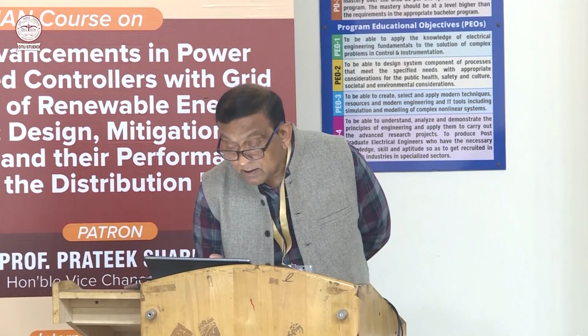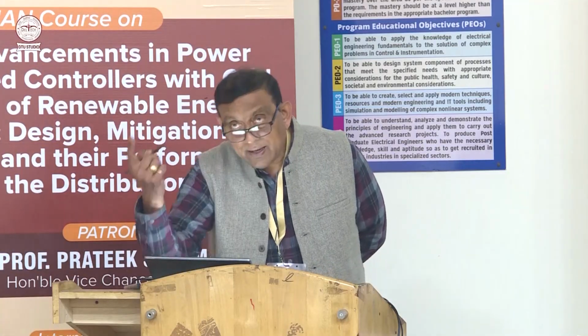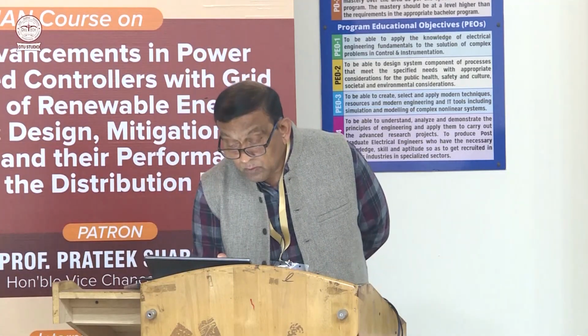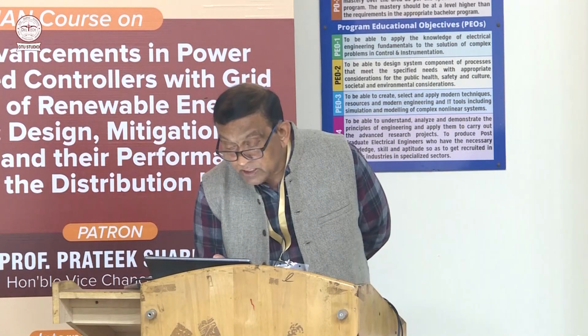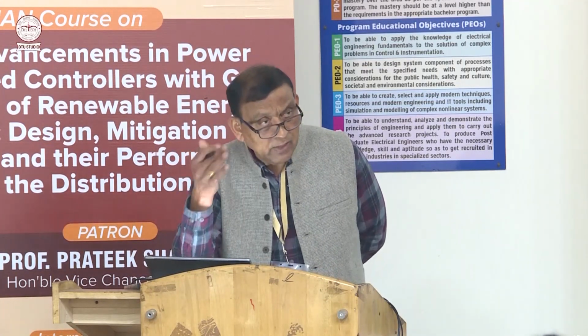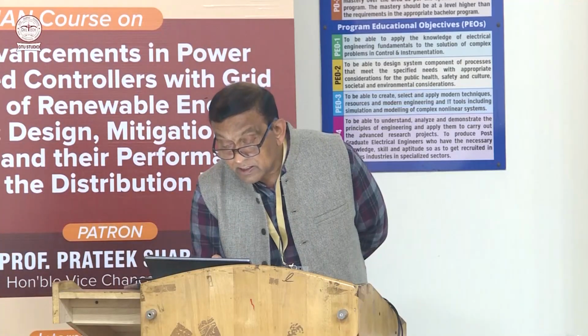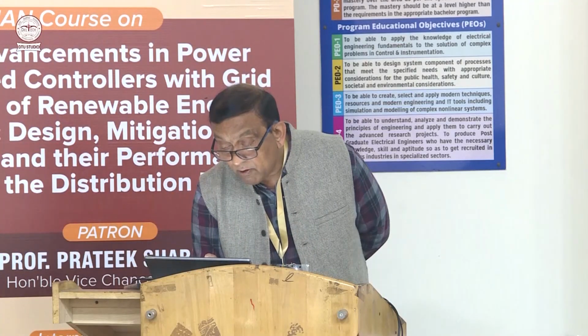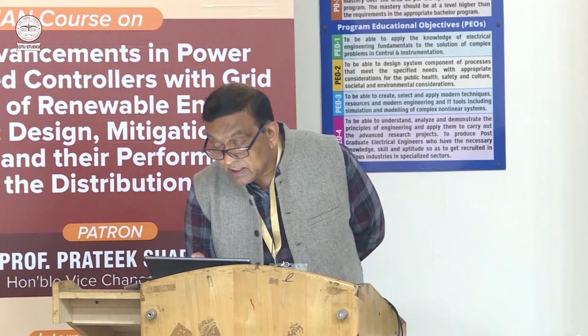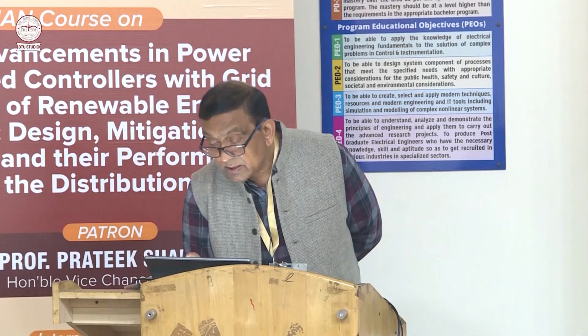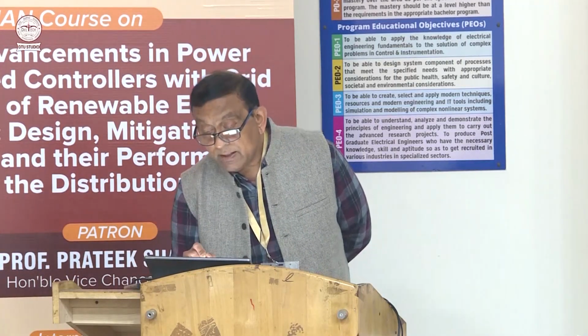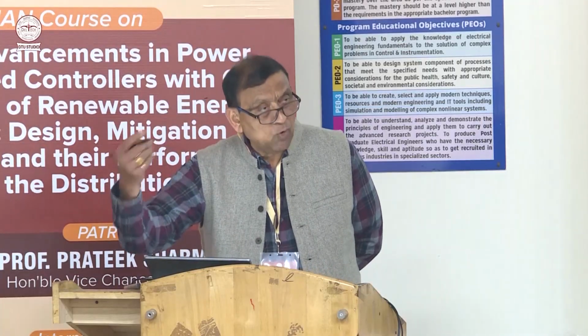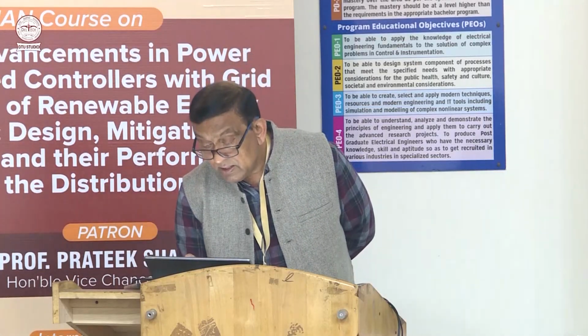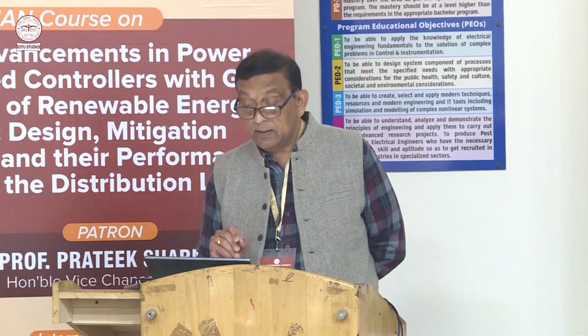So if the harmonic ranking is increasing, the limit is also more severe. For higher frequency harmonics, the limit is more severe. You see here it's 2, then from 17th to 23rd it is 1.5, from 23rd to 35th it is 0.6, and harmonic ranking more than 35, up to, we can say, the 50th harmonic, okay, this is 0.3%.